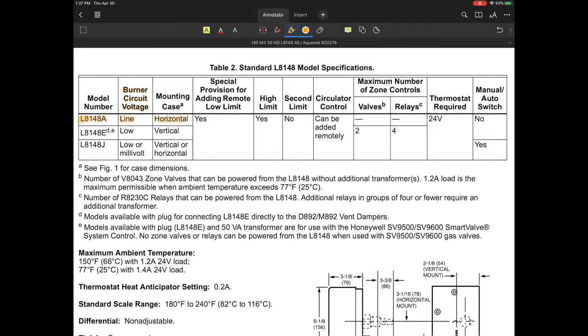This is typically something you would see used on an oil-fired boiler, the L8148A. That's a very, very common Aquastat relay. It does provide for what we talked about earlier, a low limit, and all of these will allow you to do that. All of these will. The high limit, absolutely. That's the whole purpose of the Aquastat relay: the Aquastat itself is the limiting device. A second limit, none of these do a second limit.